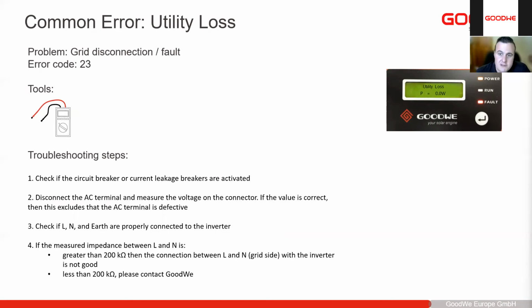Then next we have utility loss. Normally this is, especially in Africa and those places, when the utility goes offline. If we know the utility is on and we are experiencing utility loss or anything like that, we can check the circuit breaker, make sure that nothing has been tripped, disconnect the AC terminals, measure the voltage on the connector. Sometimes we have a loose connection or hot connection, it can also create problems.